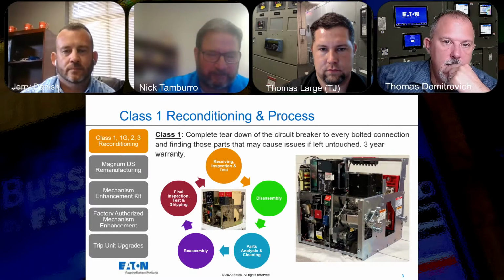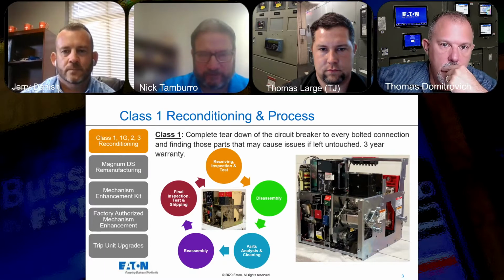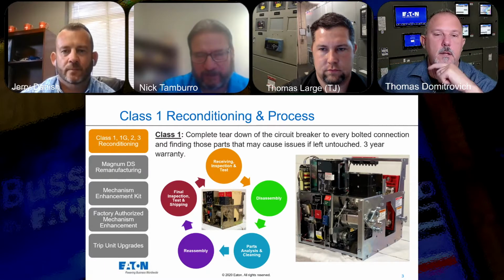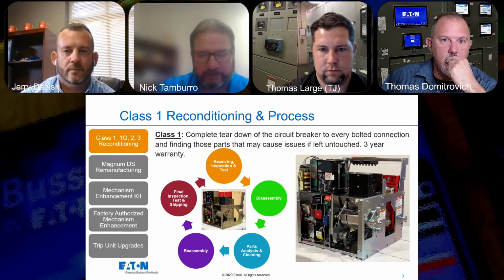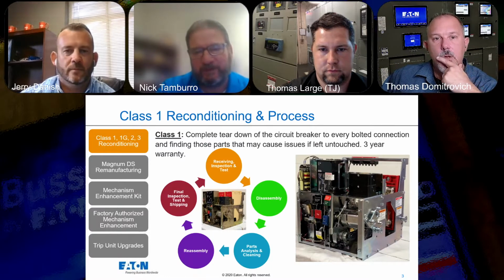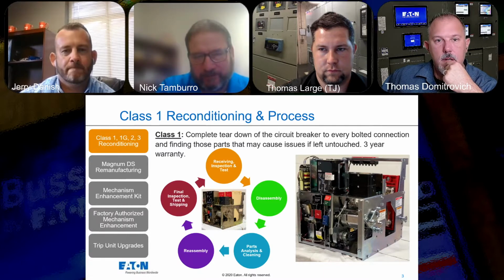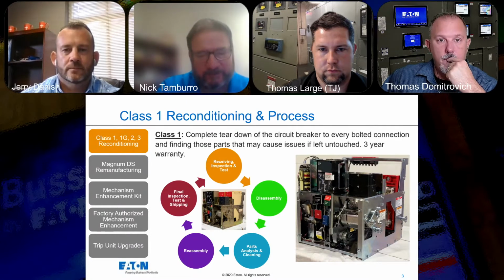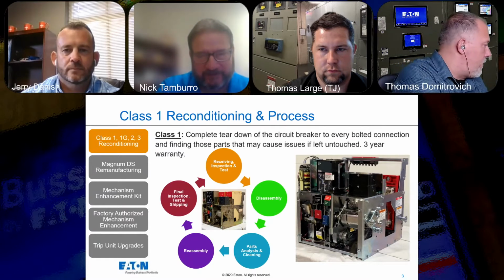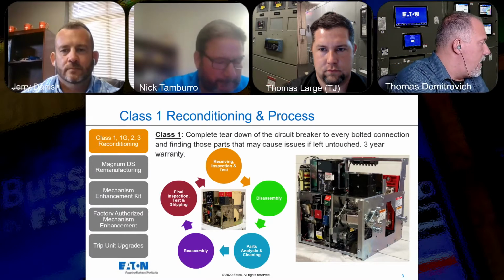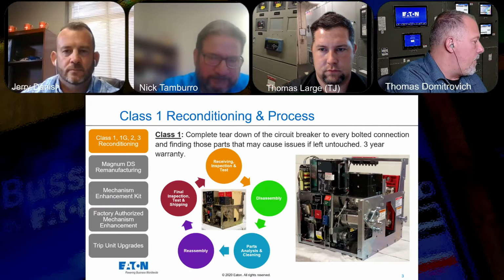You get a before and after picture on a test form that's stored in a database that you can get electronically, but we also attach them to the breakers when we ship them. You see before and after. And one thing I forgot to mention is we do a trip button force test with a force gauge before and after, so it gives you some kind of mechanical indication that the operating mechanism has improved through the cleaning, processing, and relubrication.